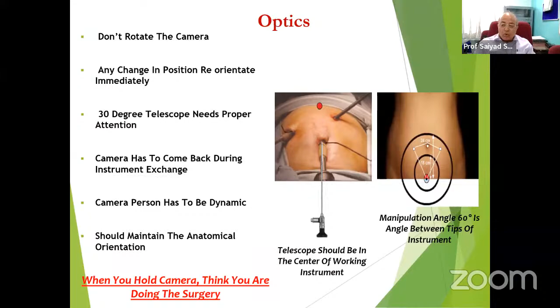One thing I will show in the picture, you see the manipulation angle. You see the camera in the center and 2 instruments away from it. If you take one angle to the right and one angle to the left, that makes 2 angles. That is known as the azimuth angle. Azimuth angle is up to 30 degree on one side and 30 degree on the other side. That means it is up to 60 degree. If a 60 degree angle is there, you can operate very easily and properly. That means you maintain the ergonomics of the position of the patient and instrument.